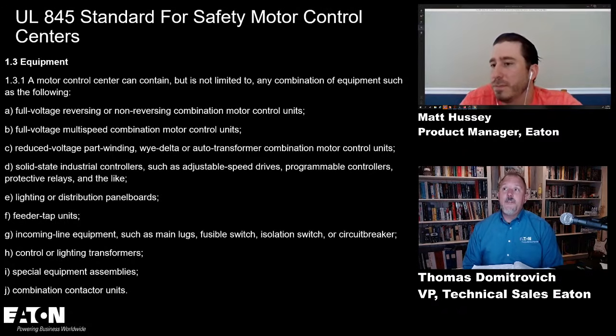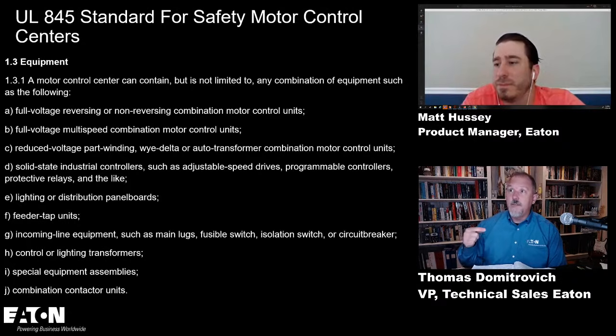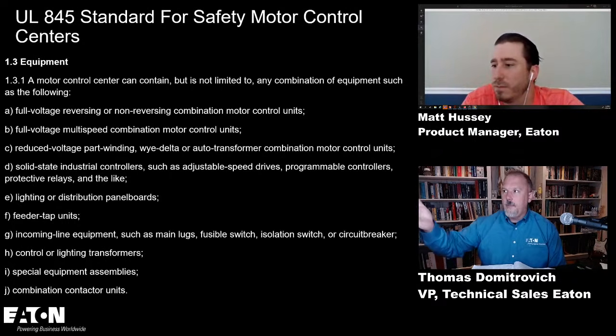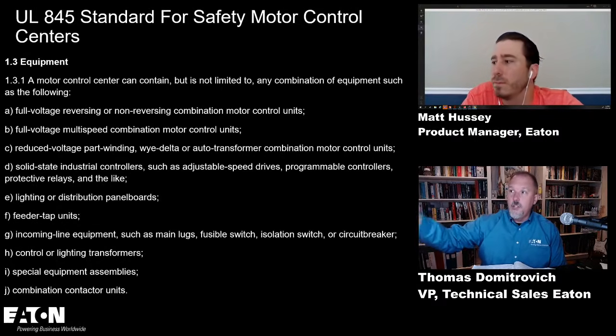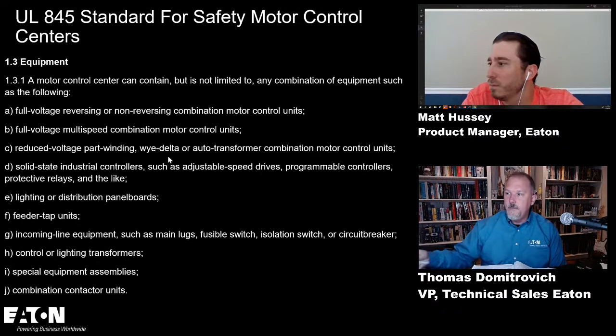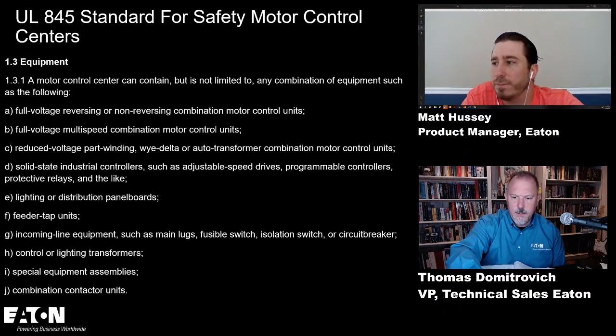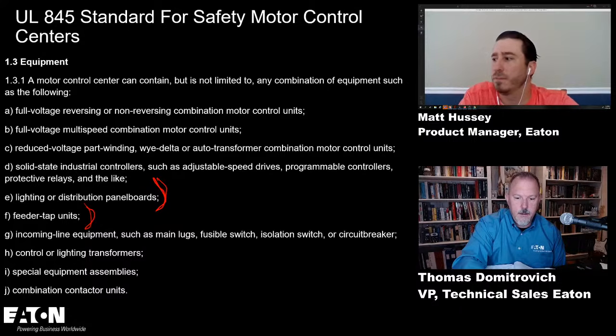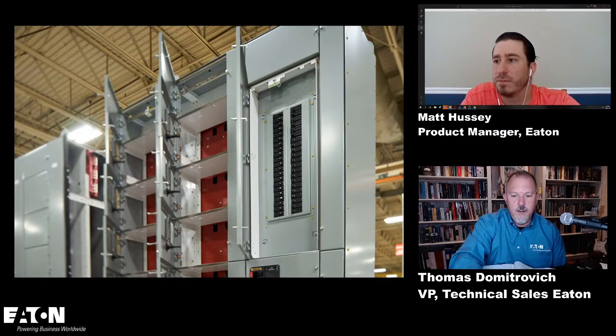So I went back to 845, and in section 1.3, it says a motor control center can contain, but is not limited to, any combination of equipment. Full voltage reversing starters, combination motor control units, reduced voltage part winding. But look at that, they have a whole bunch of stuff in here, which I was pretty surprised to see. I mean, you have your lighting and distribution panelboards right here. Feeder tap units are there. Control lighting transformers are there. Special equipment assemblies, combination contactors. So your panelboards are covered right there, and there is a picture of a motor control center with a panel.